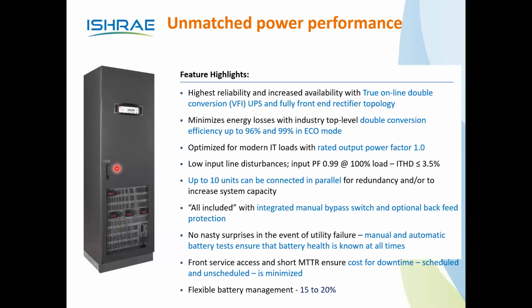Additionally, flexible battery management. This is another very important parameter. We need to specify how the battery management is. For example, if a UPS system works with 40 blocks of 12 volt, in the initial 2 to 3 years it is absolutely not a problem. Batteries are a commodity, and in the first 2 to 3 years the system will work fine. Maybe in the fourth year, 4 or 5 batteries will go bad. In that condition, it is standard practice in the market, which we have followed for the last 2 decades, to replace all the batteries, though practically only 3 or 4 batteries would have gone bad.